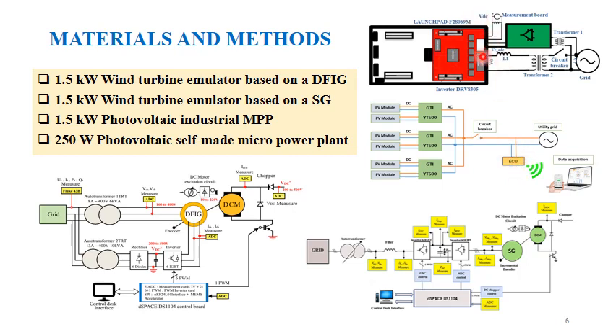The last one is a 250 W photovoltaic self-made micropower plant. We chose to build it with two interleaved step-up DC-DC choppers that extract the power from the PV. Then, the inverter stage synchronizes to the grid using a zero-cross detection algorithm and allows the injection of the reference active or reactive power.